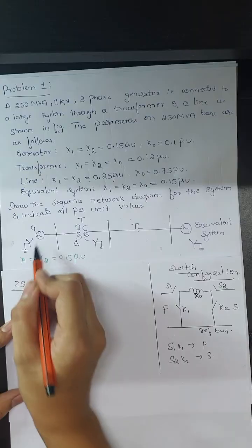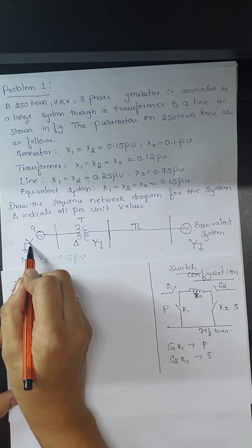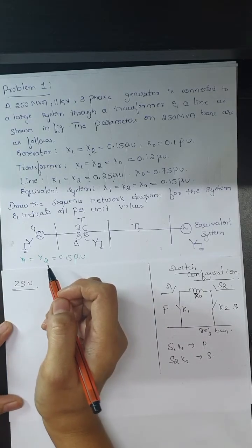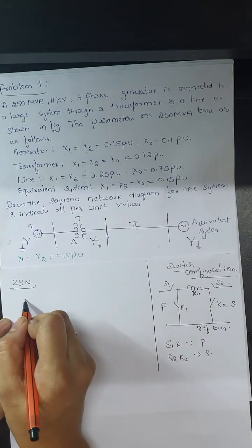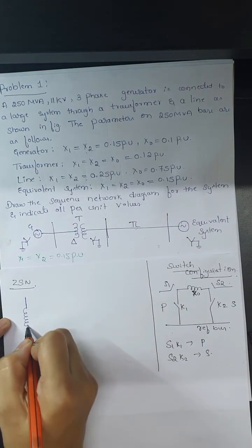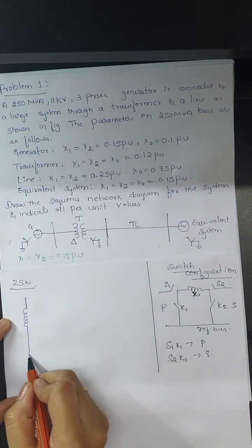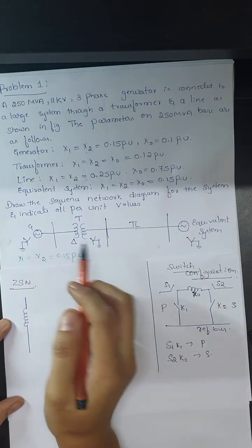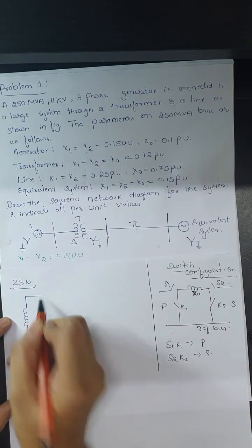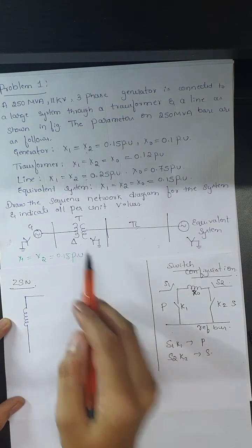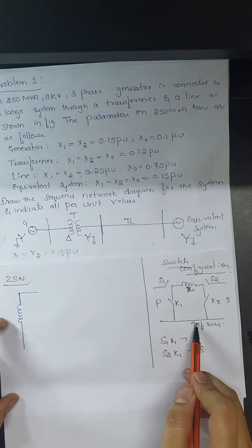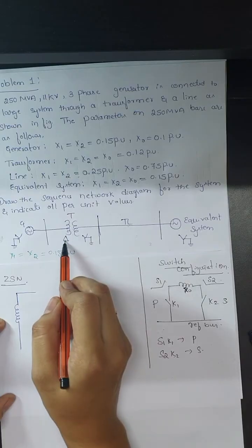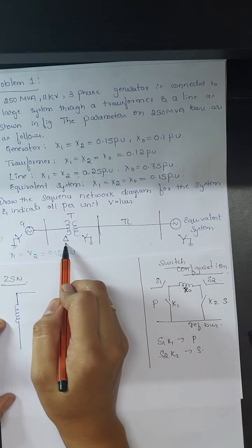For the generator, which is star connected with the neutral solidly grounded, we draw one reactance and show it with a straight line to the reference bus — indicating star connection with solidly grounded neutral, and no source voltage. For the transformer, we need to check the switch configuration. The primary side connection is delta.